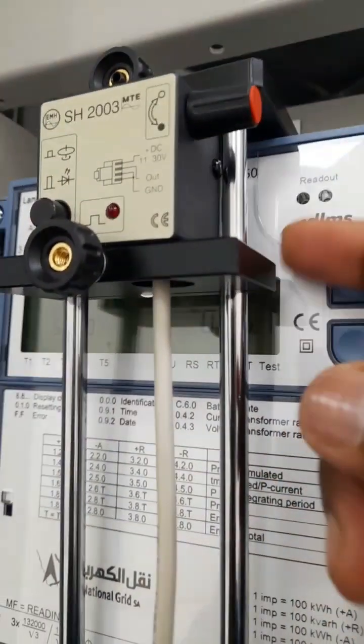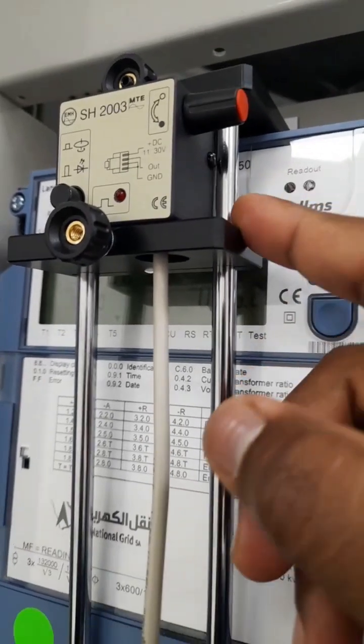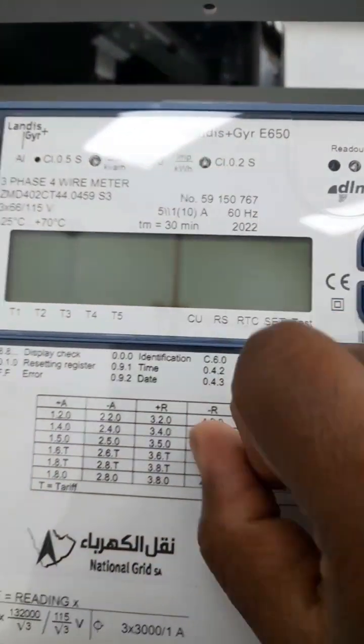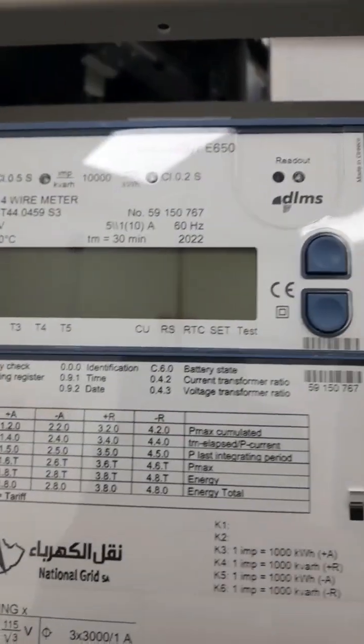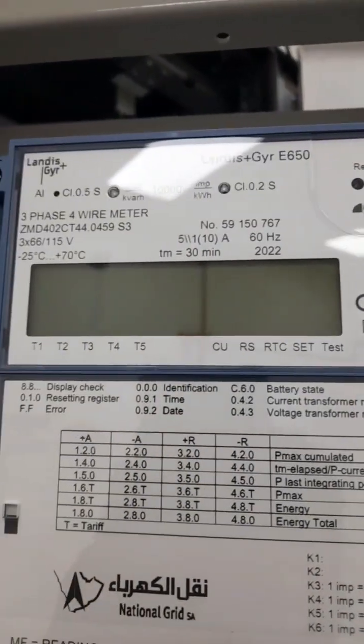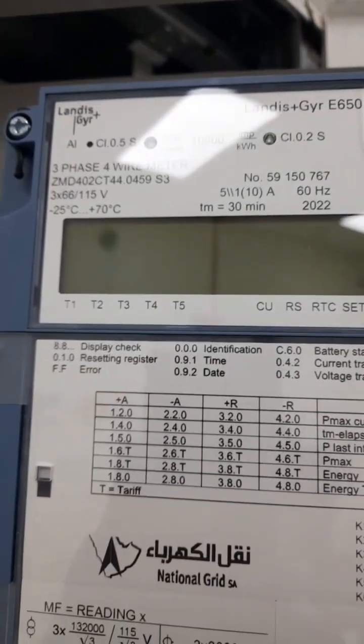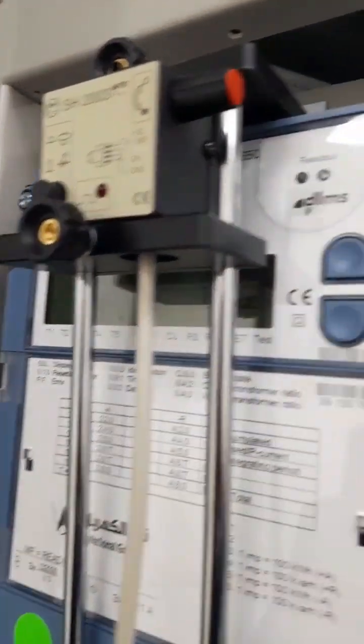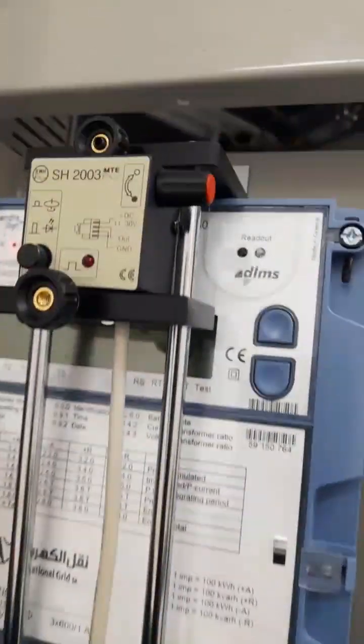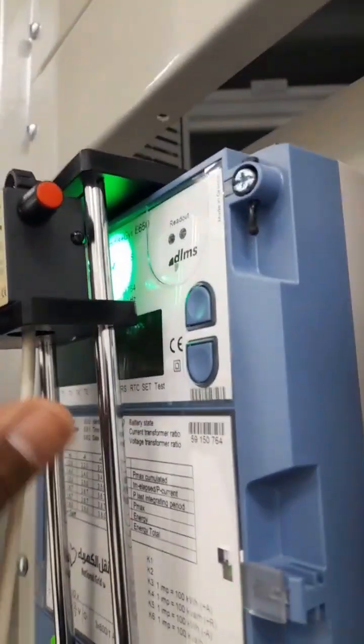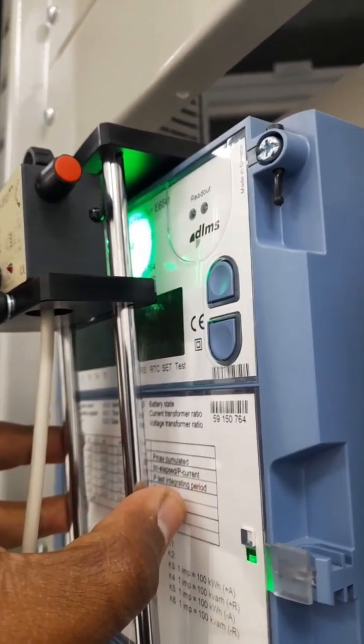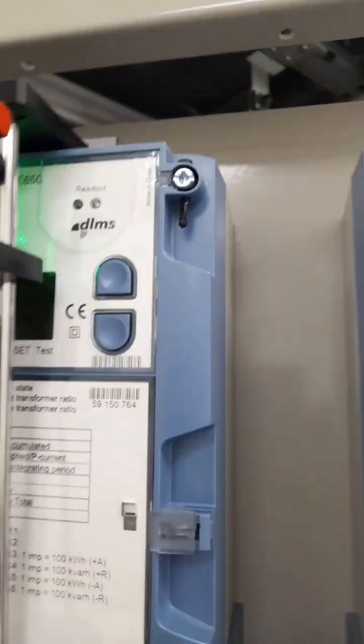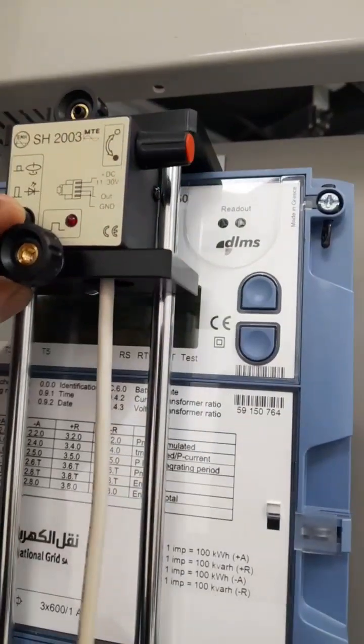While connecting this sensor, we have to make sure that the back side of the sensor has one LED that must match with this LED. If it is mismatched, your pulse will not be counted properly and you will face more error during the accuracy test. There is a green light you can use to make sure the LED measurements match.